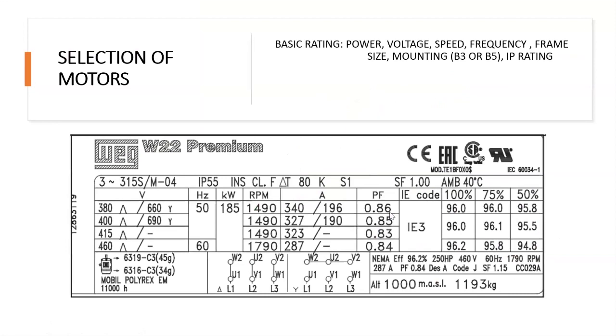So when motors are being selected for any project or any application, there are some basic ratings we look at, like the power, the voltage, the speed, the frequency, frame size, and the mounting side. That is B3 or B5, foot mounted or flange mounted, and the ingress protection rating.